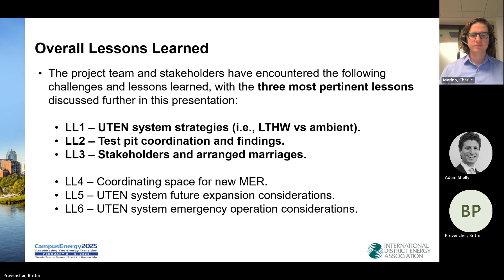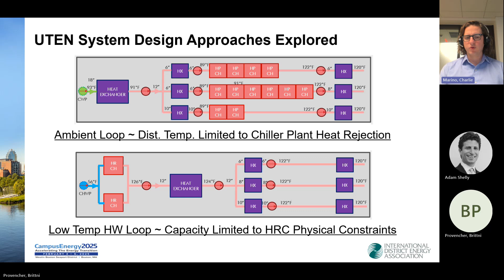One of the key components for this overall project was determining whether to utilize an ambient loop, which uses heat recovered from the condenser water loop and distributes it via heat exchangers to another set of heat exchangers to present heat for heat pumps on the customer side. I'll discuss this in more detail shortly. The other approach was a low temp hot water system, which is more tried and true for campus distribution energy networks, using heat recovery chillers to generate low temp hot water, passed through a heat exchanger serving individual customer buildings. We compared the two approaches across several conversations.